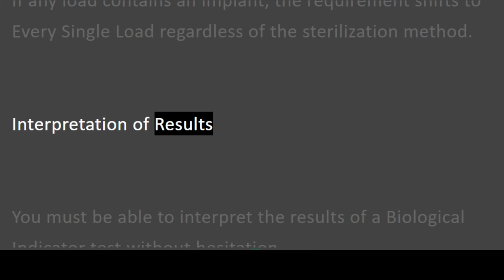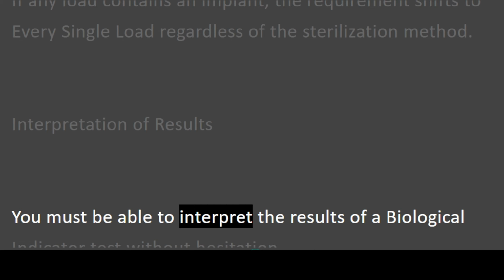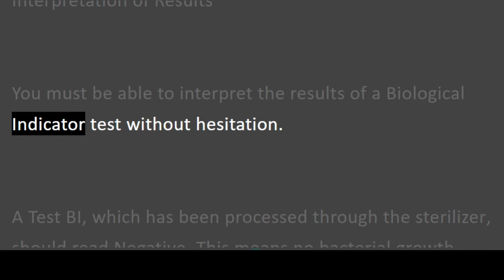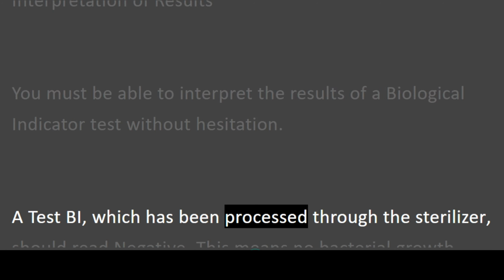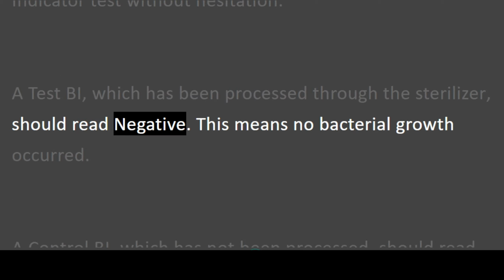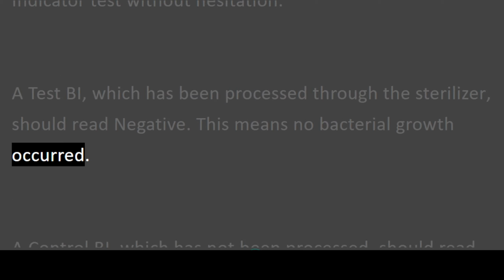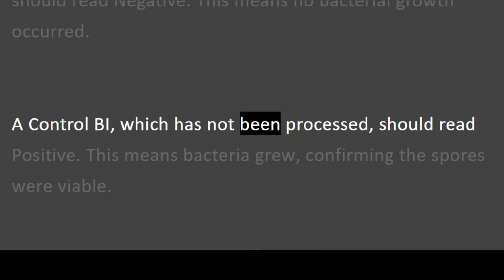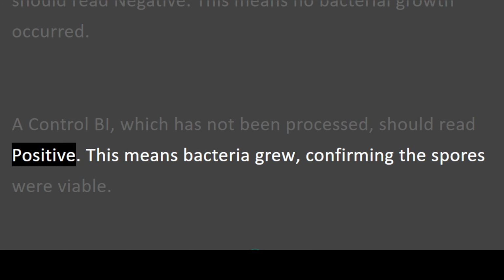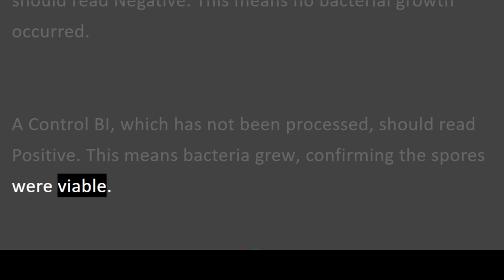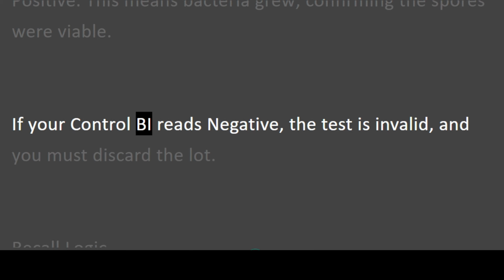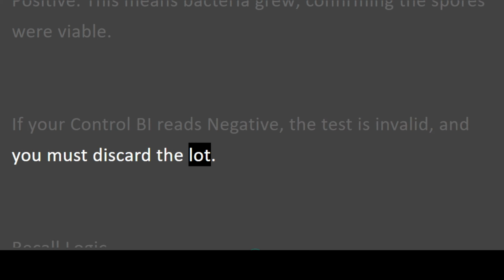Interpretation of results. You must be able to interpret the results of a biological indicator test without hesitation. A test BI, which has been processed through the sterilizer, should read negative. This means no bacterial growth occurred. A control BI, which has not been processed, should read positive. This means bacteria grew, confirming the spores were viable. If your control BI reads negative, the test is invalid, and you must discard the lot.